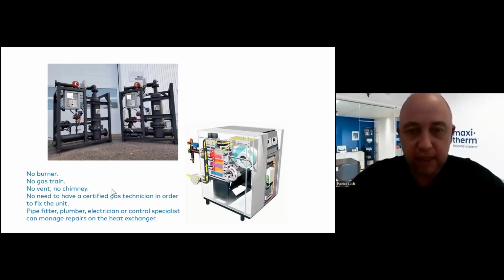So I'm telling you that this unit here, robust as it is, made in the US, TEMA standard, not ASME, which is a higher standard, will last for a much longer time than any condensing boiler in the market. Way less, the longer lifespan.